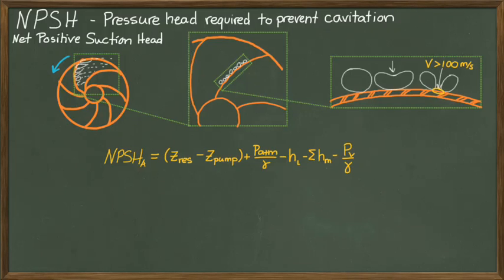The difference in elevation between the reservoir and the pump is an engineering design choice we make, which also has an impact on the pipe diameter, length, and minor losses. We have tables that help us look up the atmospheric pressure as well as the vapor pressure as a function of water temperature. When we calculate the friction losses, we must use the Darcy-Weisbach head loss formula, because unlike the Hazen-Williams approach, the Darcy-Weisbach formula accounts for temperature variations in the fluid. It can also be applied to more fluids other than water, so if you're pumping oil, you can use Darcy-Weisbach.